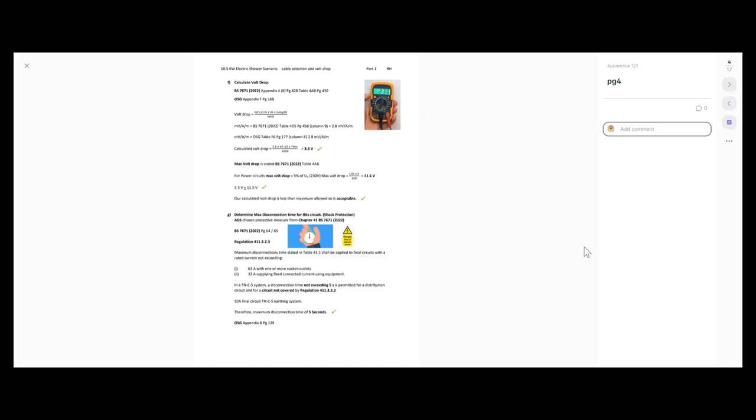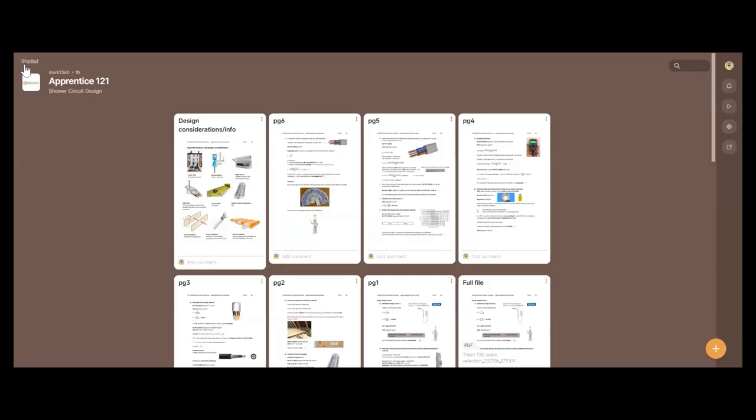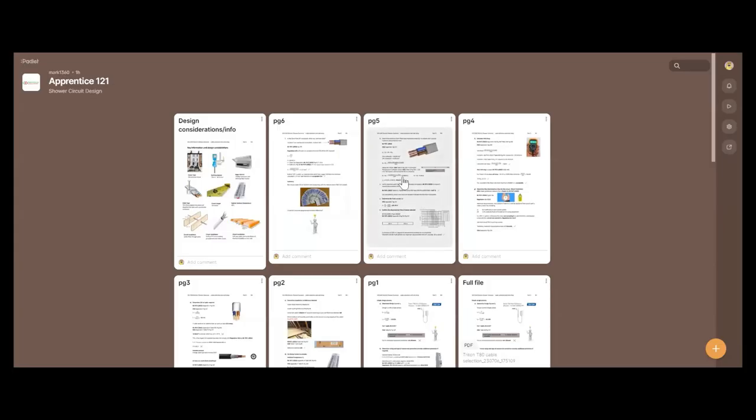I've got to make sure that our RCBO's circuit breaker side will disconnect in a maximum of five seconds. To do that, I need to consider what my maximum earth fault loop impedance value is to achieve that five-second maximum disconnection time. I need to find this value of ZS and compare it with the maximum value. To calculate ZS, I can use the formula in the on-site guide on page 217: ZS equals ZE plus R1 plus R2 — the resistance of your line conductor and your CPC.